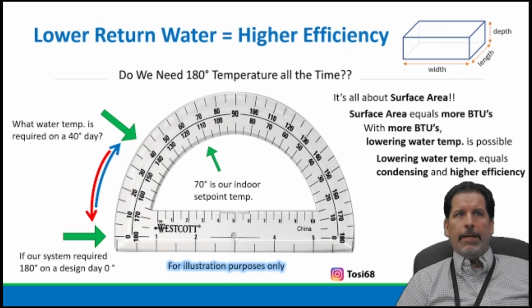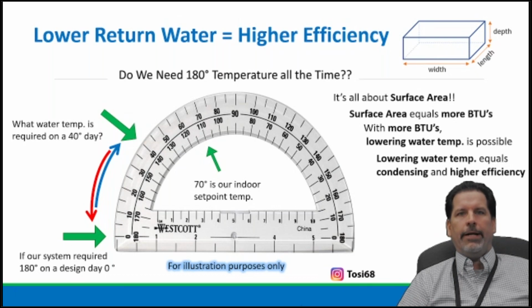So, look, 70 degrees is our indoor set point temperature, right? If that's what comfortable is for your customer on a winter's night, then understand that if we're delivering 180 degrees and it's 30 out, you have an oversized boiler, you have oversized emitters, call it baseboard, let's say, all around the house, you're going to have a really inefficient, noisy, cycling system.